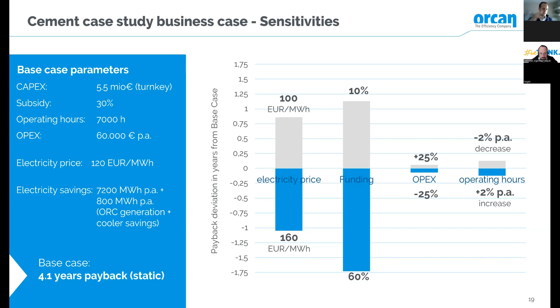There is funding available, up to 60% sometimes even, that's why we asked the question before. It's also interesting that OPEX doesn't really have a heavy impact on payback since it's rather low, as mentioned before. Operating hours also don't have such a big impact, since we can deal with that. If there is less heat, we turn off 1-2 machines; if there is more heat, we can add machines, which we're currently doing.